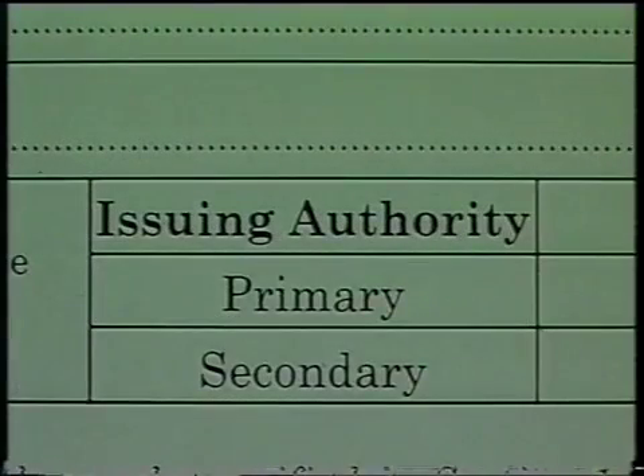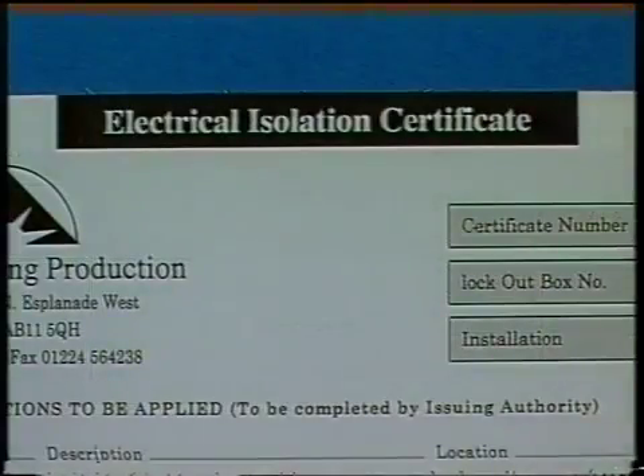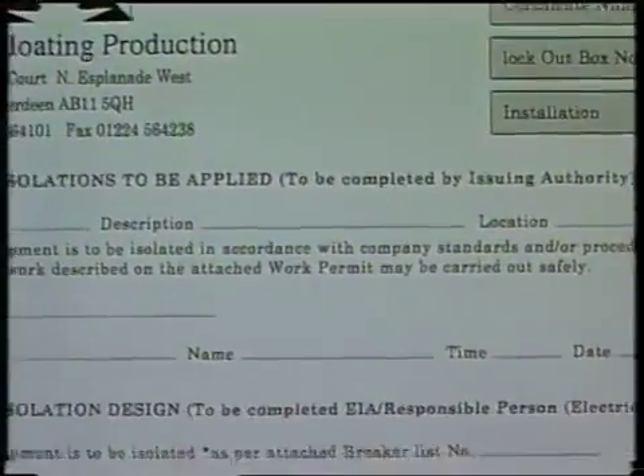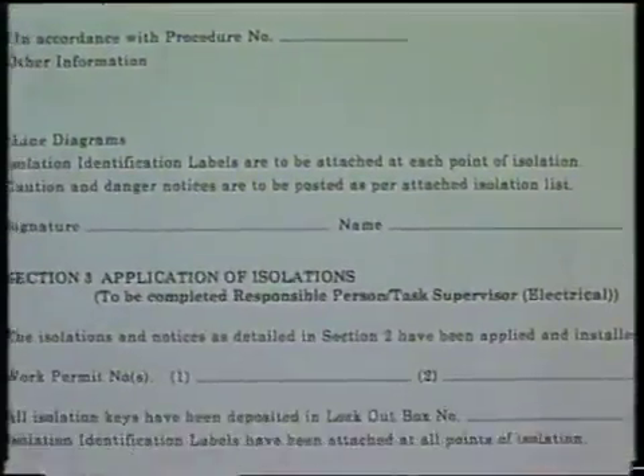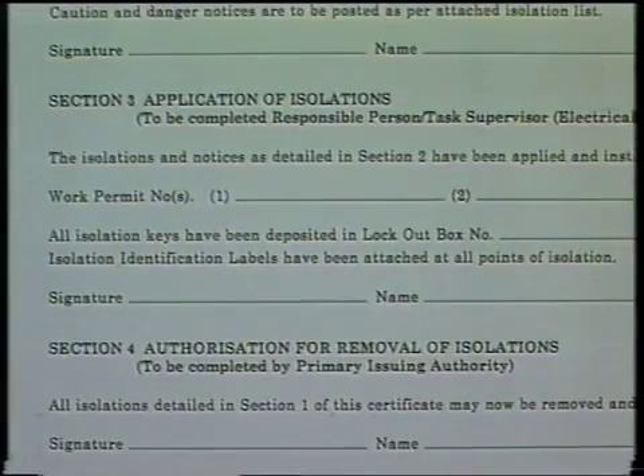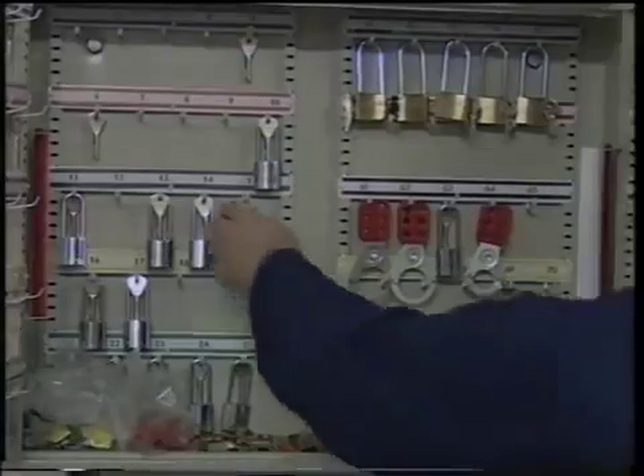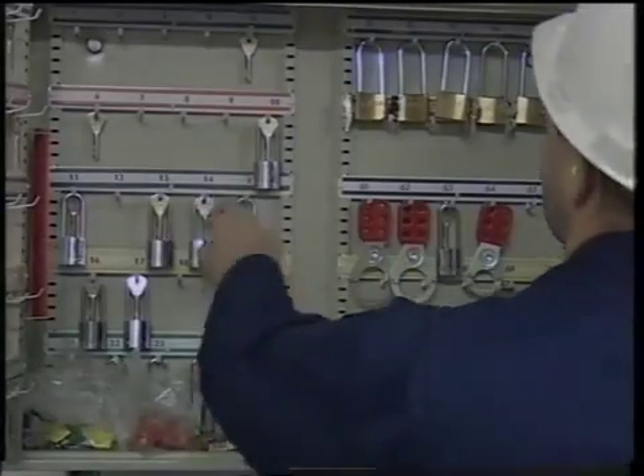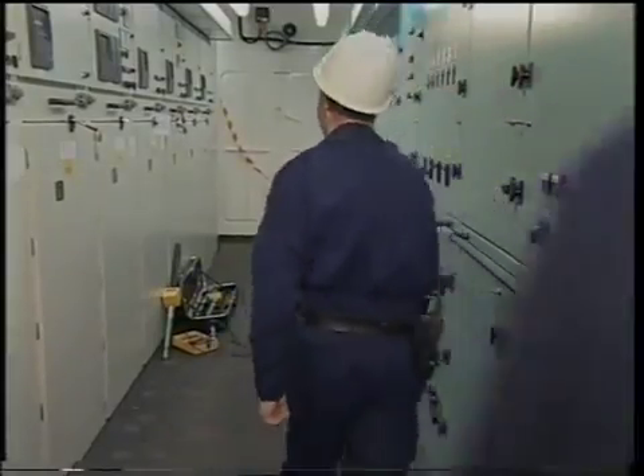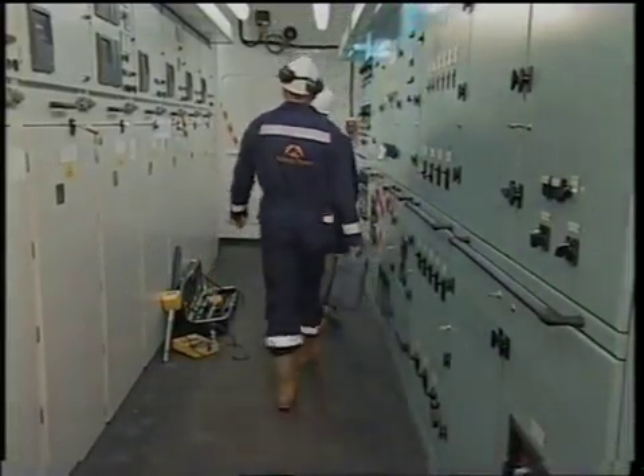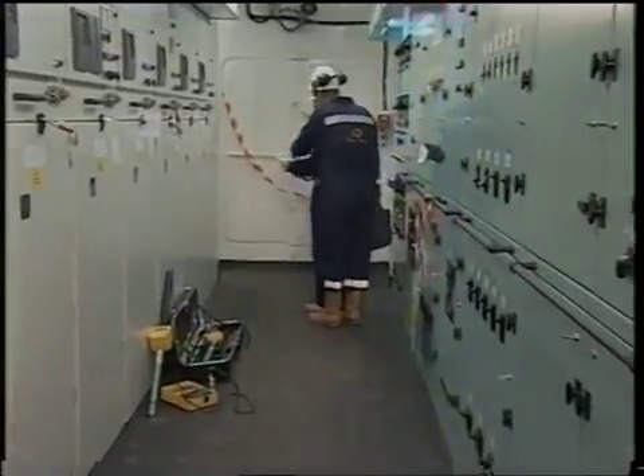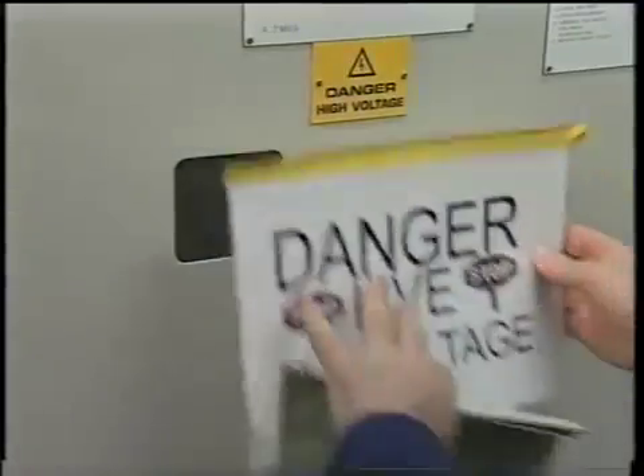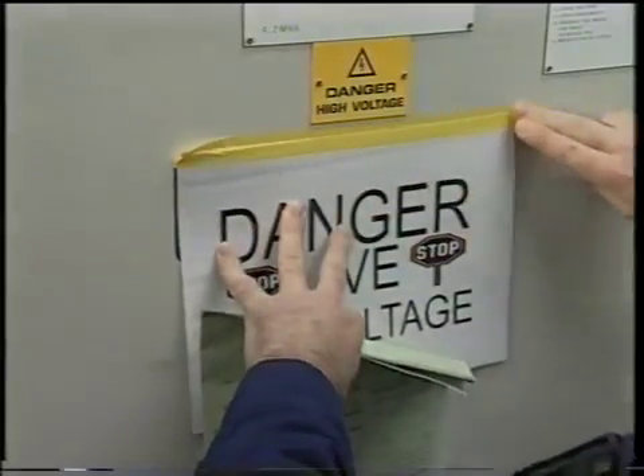The electrical work permit request must be countersigned by a senior authorized person, usually the chief engineer, and the duty watchkeeper. An electrical isolation certificate is issued listing where the HV circuit is to be switched off, isolated, locked off and earthed, and in which lockout box the isolation keys have been deposited. The CETO now collects keys from the lockout box and a number of isolation warning tags and safety notices. He and his assistant proceed to the relevant circuit breaker. It's important to fix notices to warn all colleagues of the work being carried out.